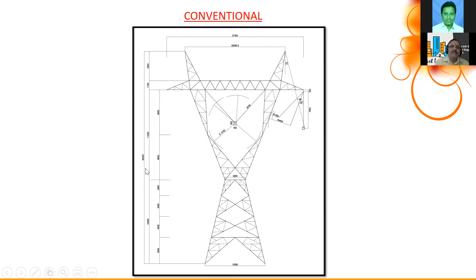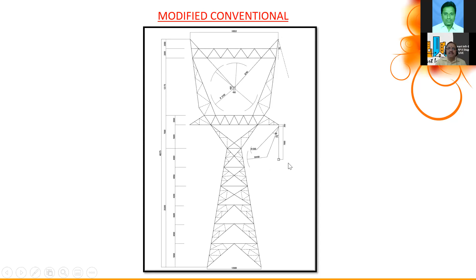You can see the height of the tower is 40 meters plus 45 meters for a single circuit. This is a modified conventional delta configuration. These three conductors, and this is the ground wire, called the shield angle. This shield angle means the probability of lightning striking within that angle, so 15 degrees is what we consider, and it protects the conductor from getting charged.